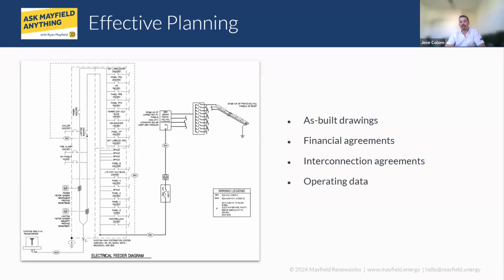We've got a few different options, and depending on the system configuration or the as-built, that's how we determine which is the best SMA inverter to use for each application. Another thing we look into is the interconnection agreements. We might not specifically ask for them, but we do ask, for example, when was the system installed initially, since that might have been prior to rapid shutdown requirements if it's a rooftop system, or right after, or if the customer needs to bring the system up to code when repowering. This all depends on the different AHJs out there and whether they grandfather back to the day the system was installed or not. Those are the kinds of things we look into when working on repowering with string inverters.